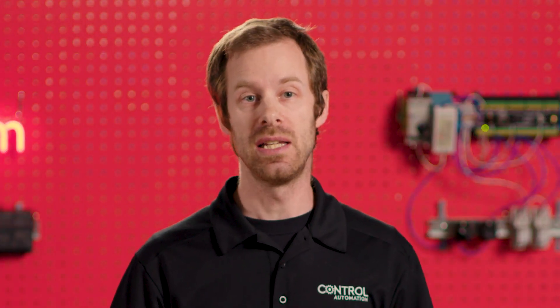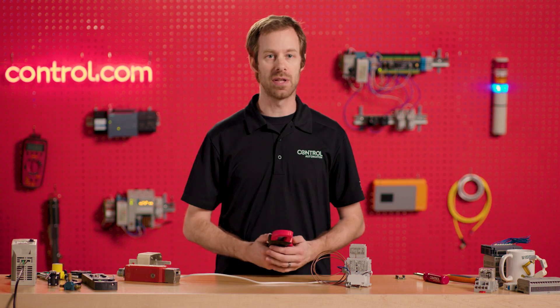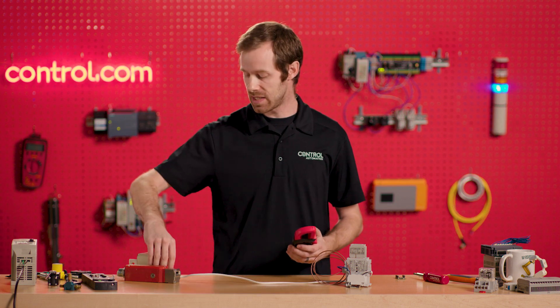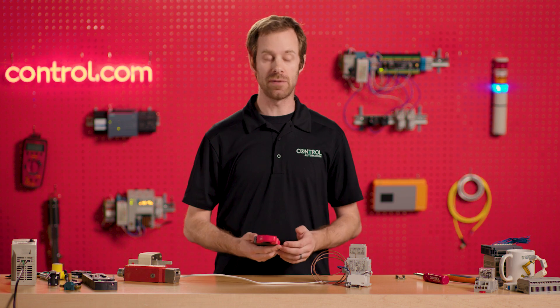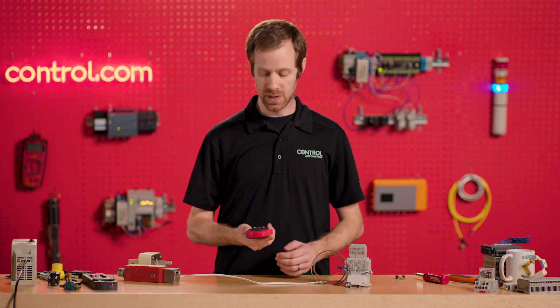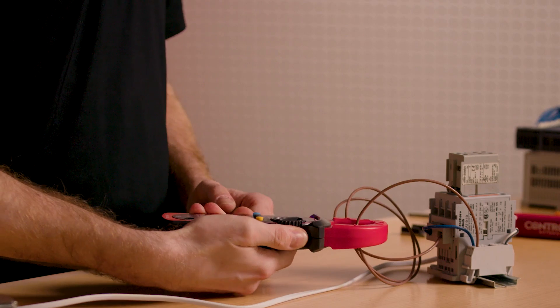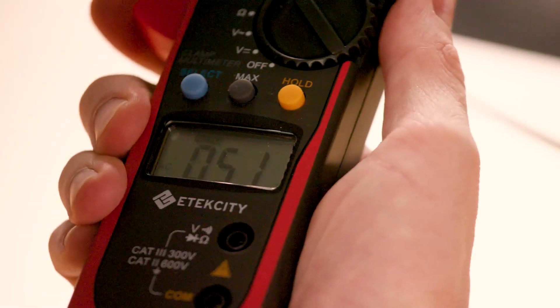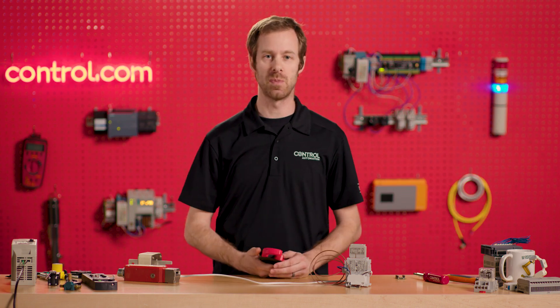This one is quite precise, but sometimes the current that we're testing needs a little bit of extra precision. So here I have a contactor that's powered by 110 volts AC. When I turn it on, I want to measure the amount of current going through the coil. So I turn on the clamp meter and I measure one of the strands. And I can see that I have about 0.05 amps. That's a very small quantity, as I would expect for a small contactor.